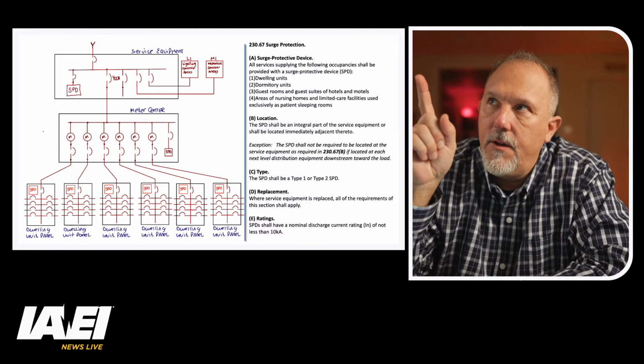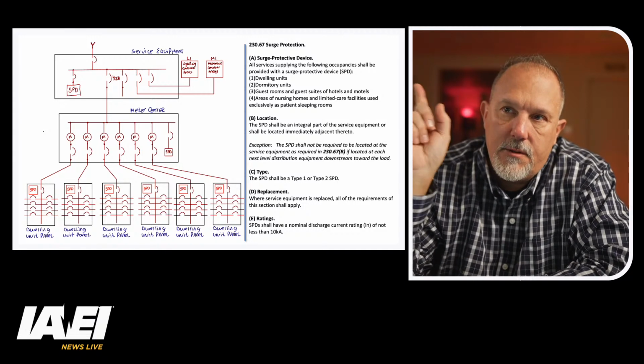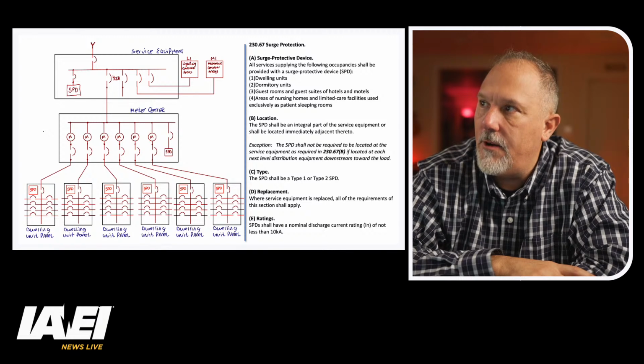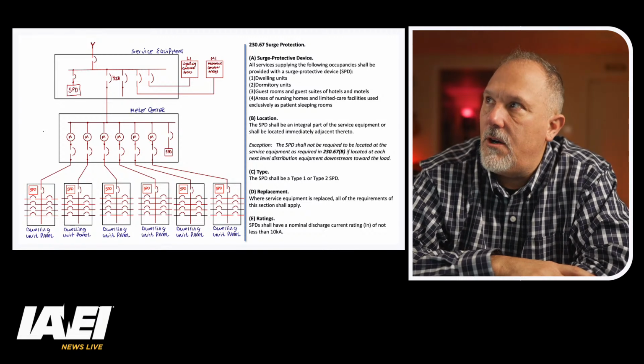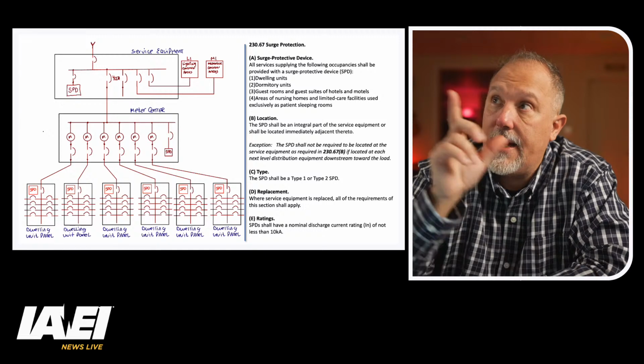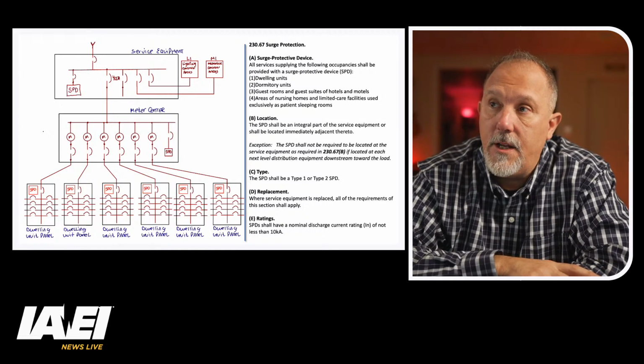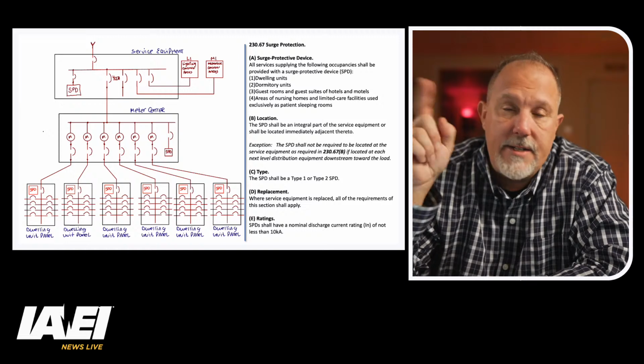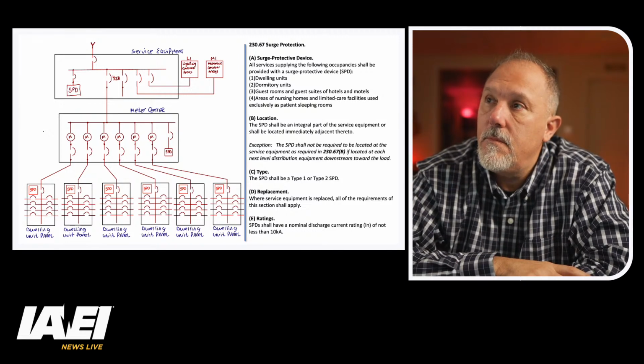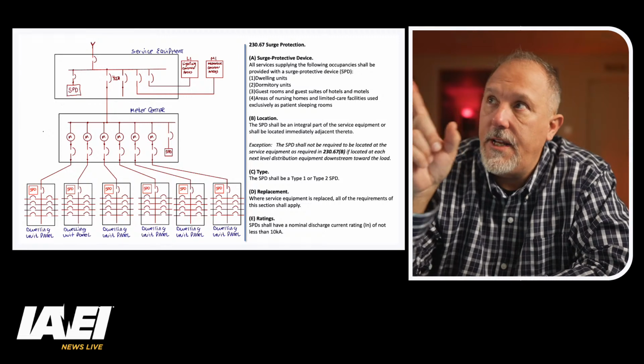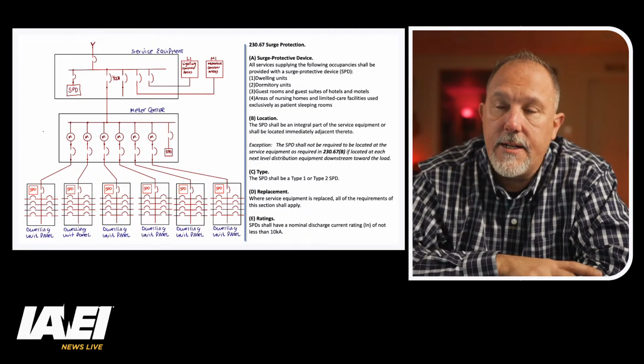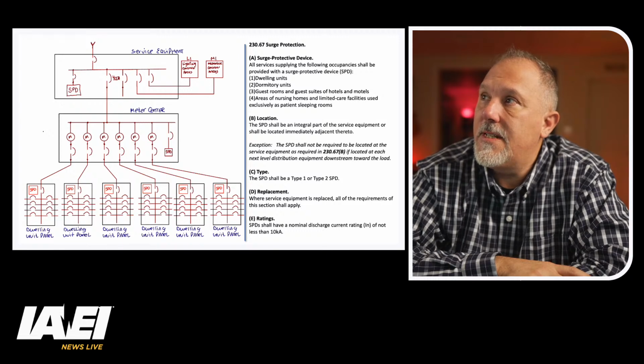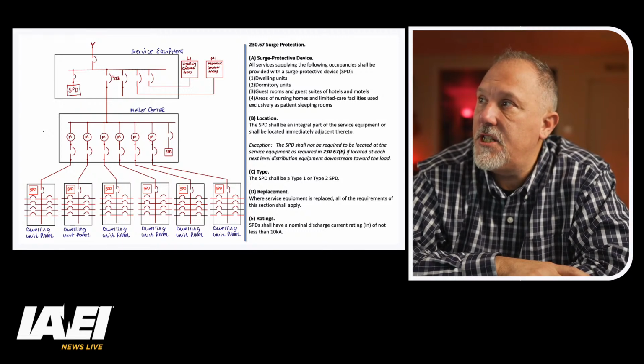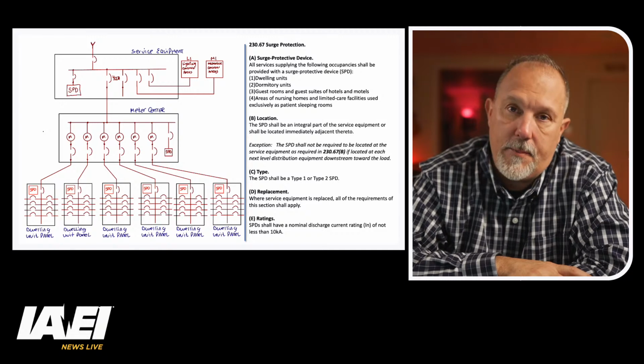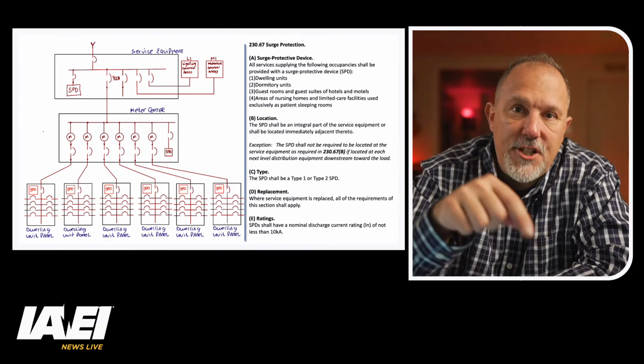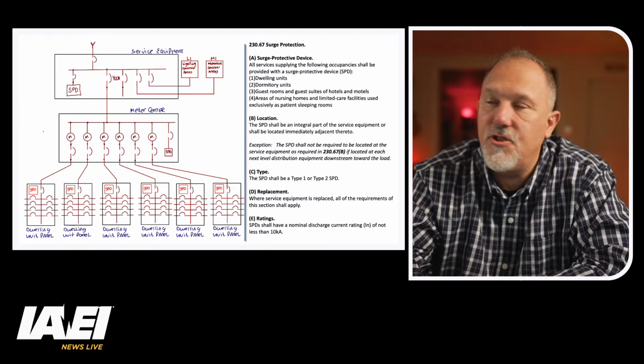If I'm in the service equipment, I'm following Article 230, so there's the language that I would be required to follow. It says all services supplying the following occupancies, and that service supplies the dwelling unit occupancies listed down there on the bottom. So that service would need to have an SPD, which is indicated there. Now there's an exception for the location. It says the SPD shall not be required to be located at the service equipment if located at each next level distribution equipment downstream toward the load.